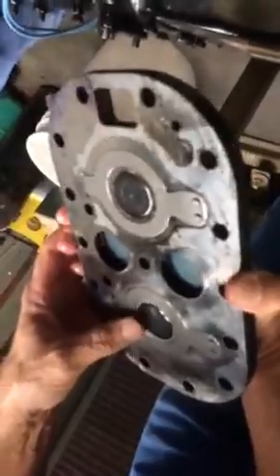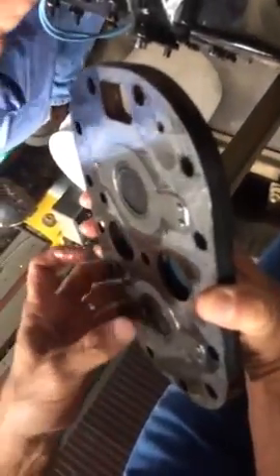So now we're checking the reeds. It doesn't look like there's any obstruction in there. This is your suction reeds, this is your discharge reeds. So for the YouTube people out there — suction and discharge. There you go. The puck. Nice, huh? Discus.